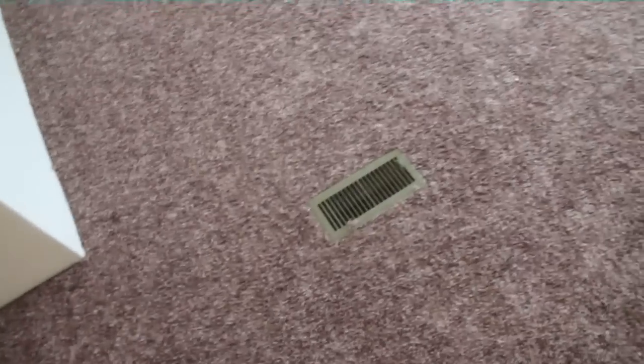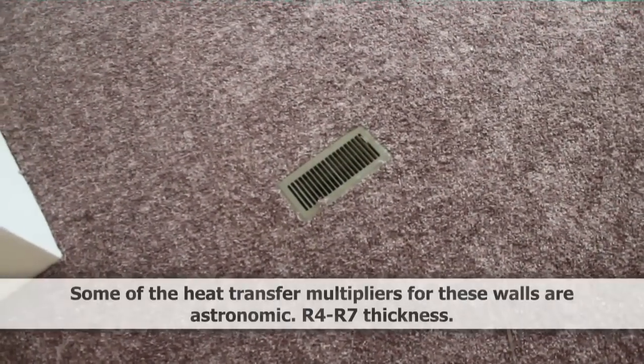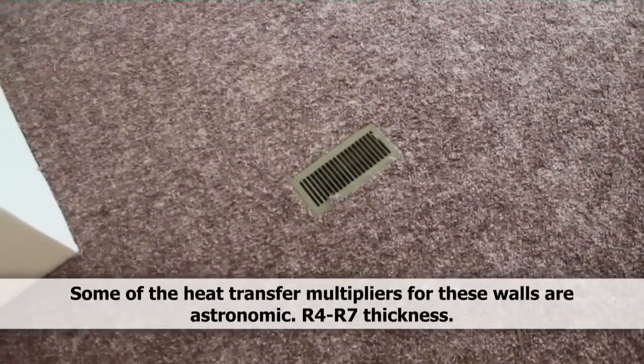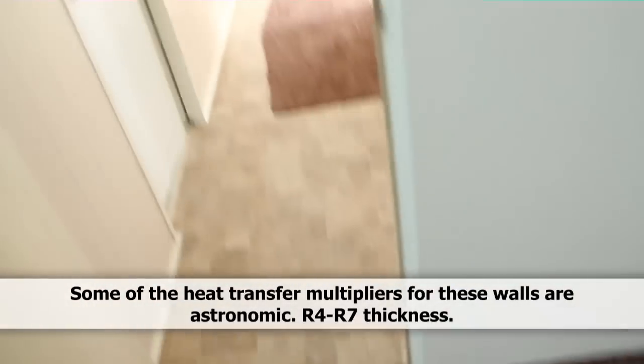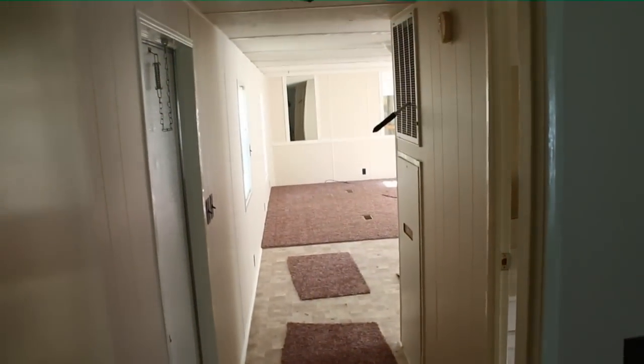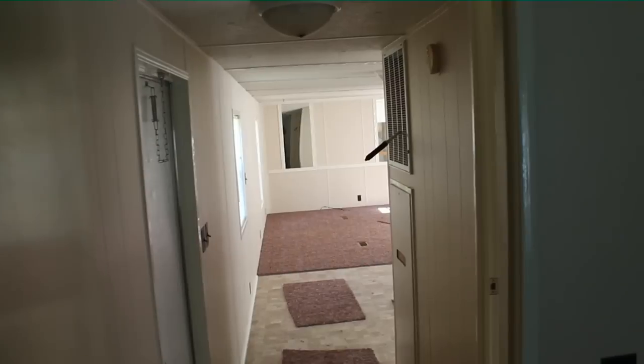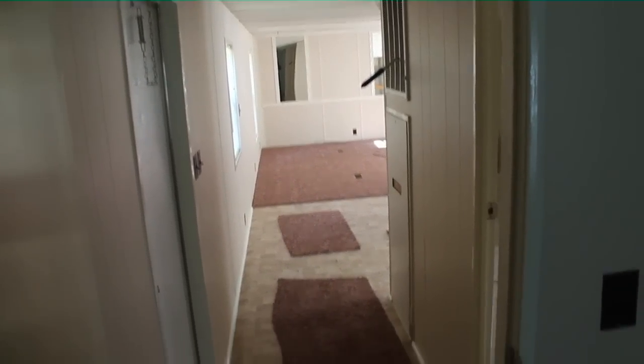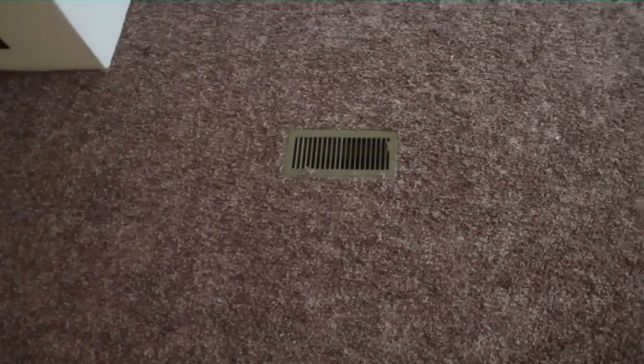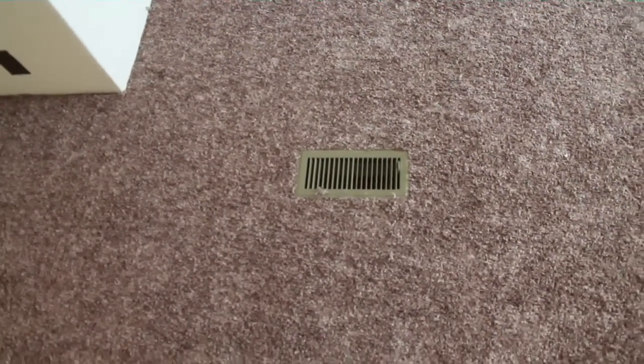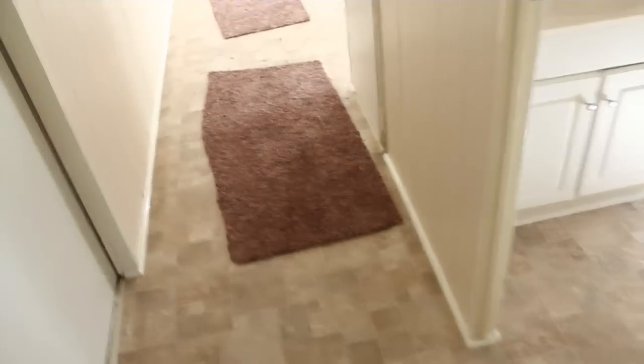And that's a pretty good location for these. Most of these trailers have 3-ton units on them because the heat loss, or heat gain should I say, in these walls is substantial. You'll have walls that are insulated to 1/3, at the best a half as good as a standard house. Most of the time when you shut these ACs off, you can feel the heat creeping back in through the walls. A lot of them have 3 tons, but none of them have the ductwork for 3 tons. And none of them have the ductwork to really support 2.5 tons. That's what we have here, because all of the 3-ton machines are just choked off for air.